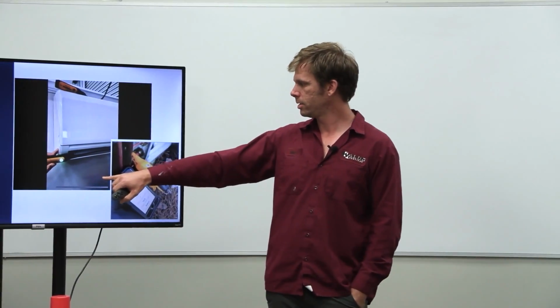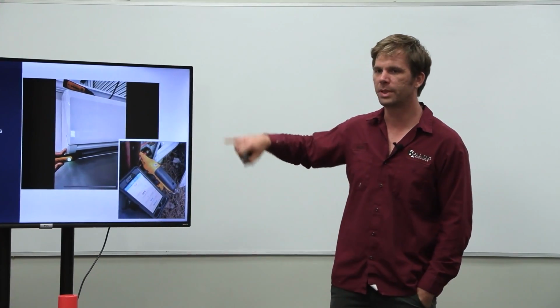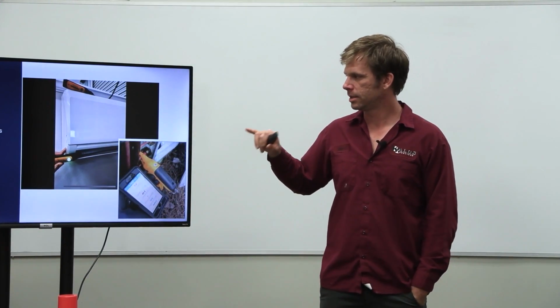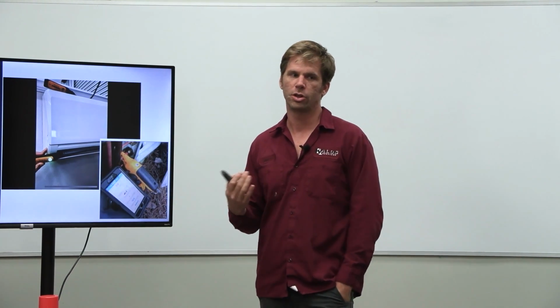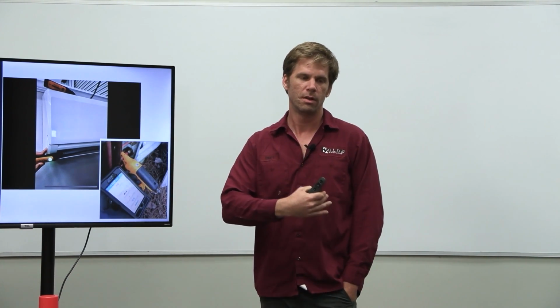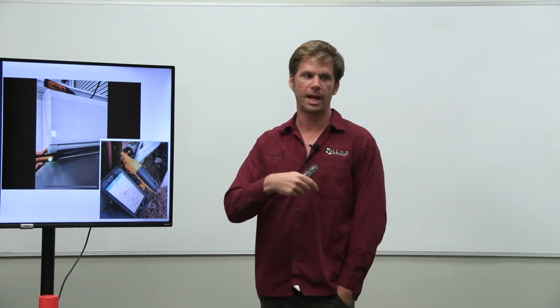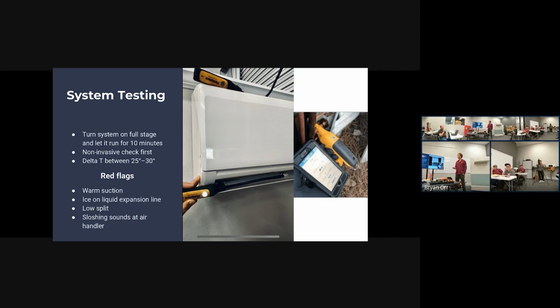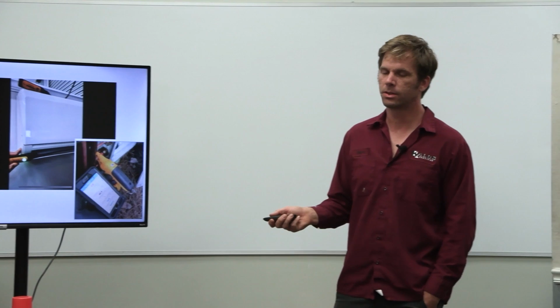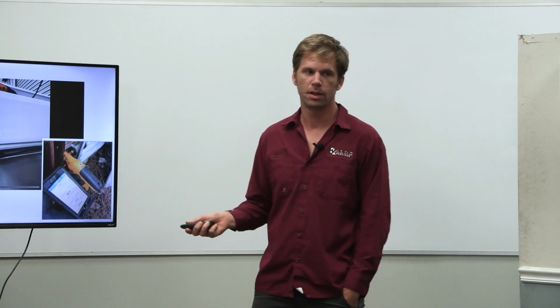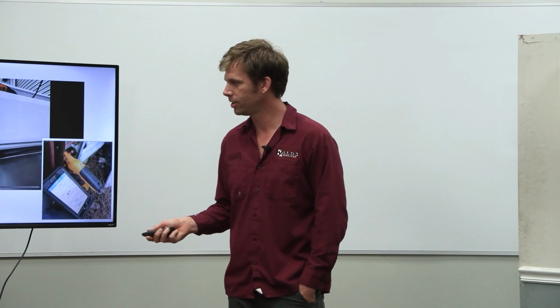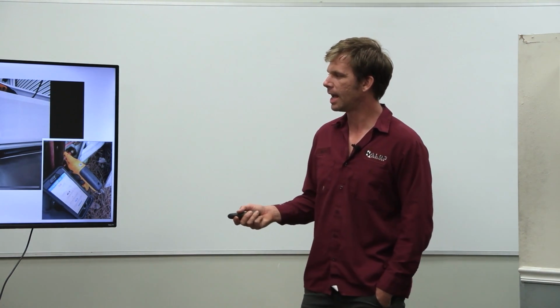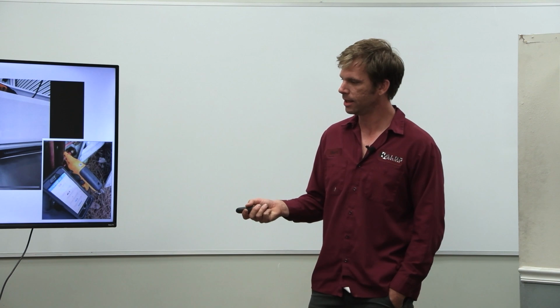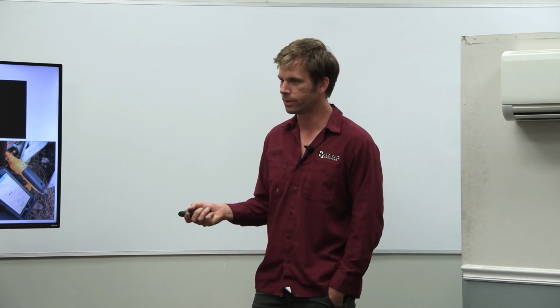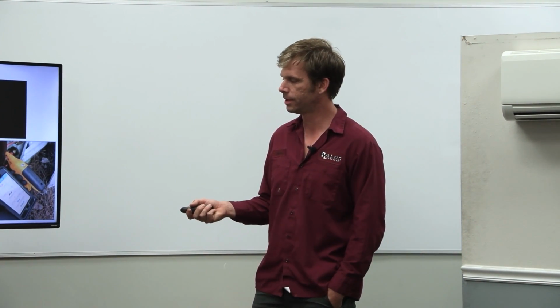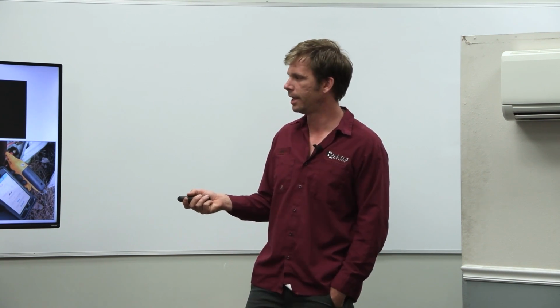So if you've got ice on your expansion line, the liquid line that comes up in, the smaller line, that's a real clear indication that you are low on charge and it's actually starting to flash and freeze right after the expansion valve. Again, not necessarily only low on charge. You could have a screen issue, but low on charge is the primary issue. Everybody always thinks it's only one thing. In the last 10 years, it has been an electronic expansion valve like once or twice. So seriously, there's no way to know that, ever.